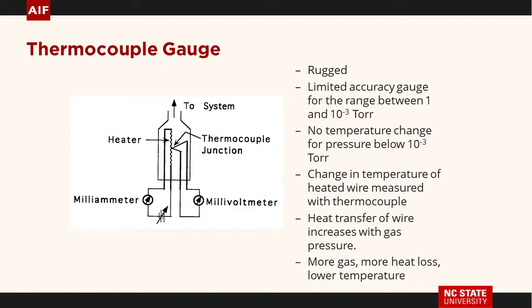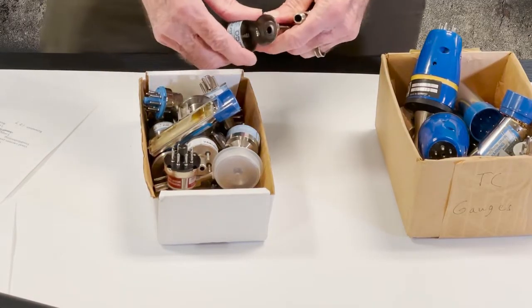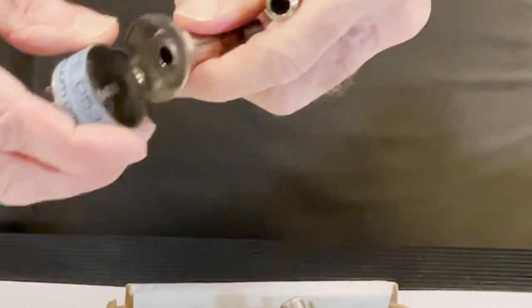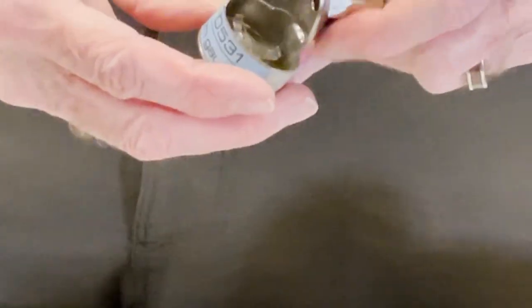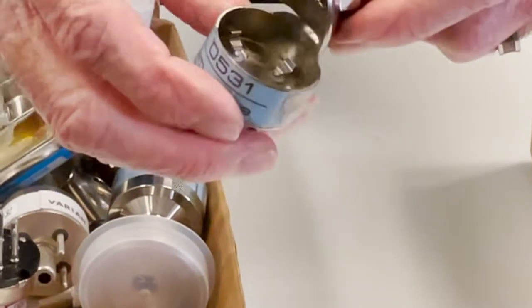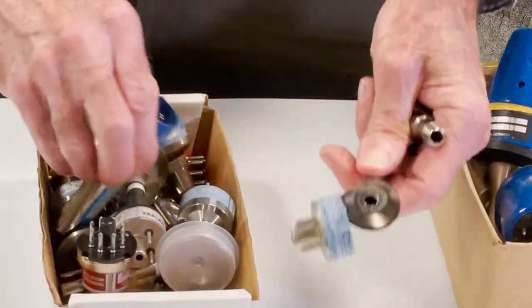Now we're on slide 90 and the thermocouple gauge. It works pretty simply: you have a set of two pairs of wires — one's a thermocouple and the other is a heater. The change in temperature of the heated wires is measured with the thermocouple, and the heat transfer of the wire increases with gas pressure. When you look inside one of these, you see four connectors and two wires that touch in the middle — that's it. This may cost you a couple hundred dollars, but that's all that's in there.